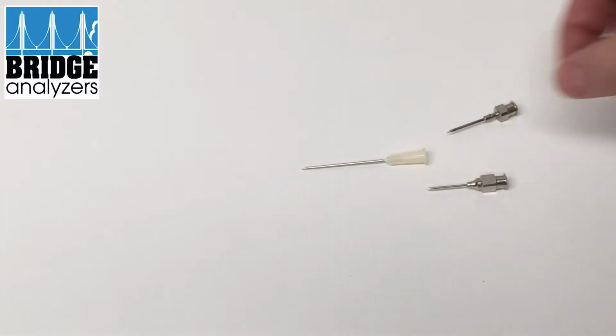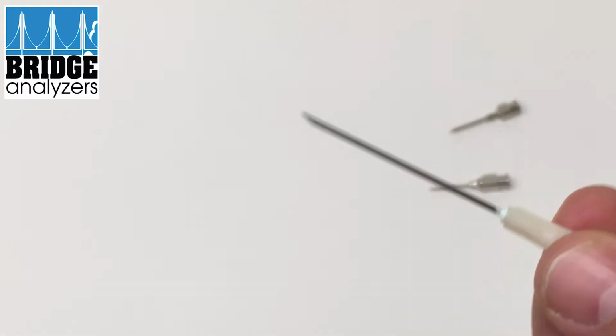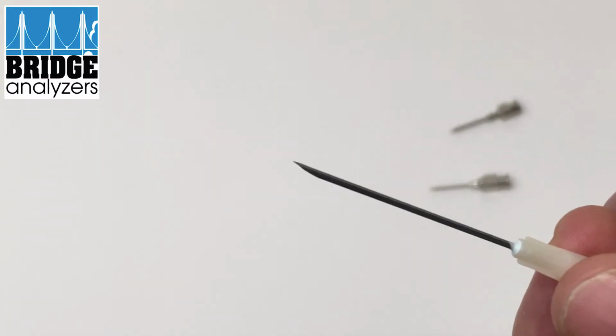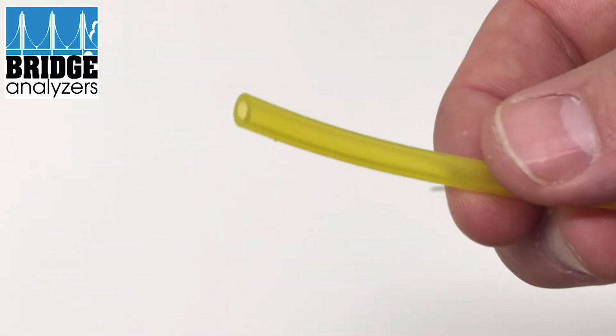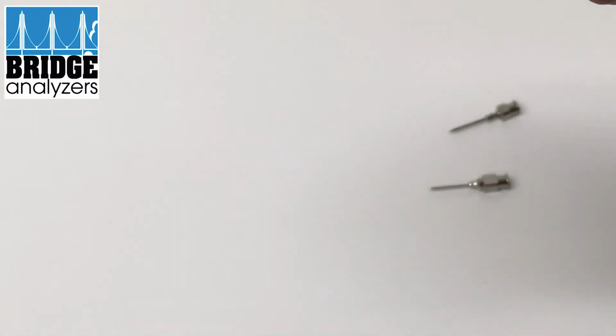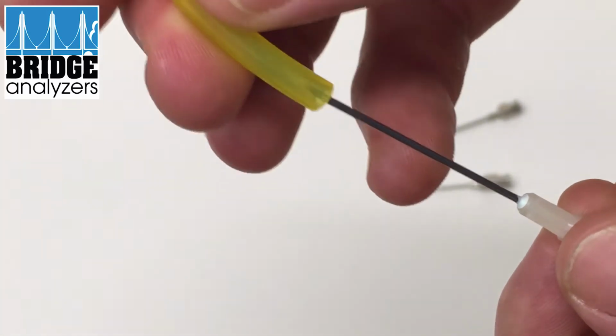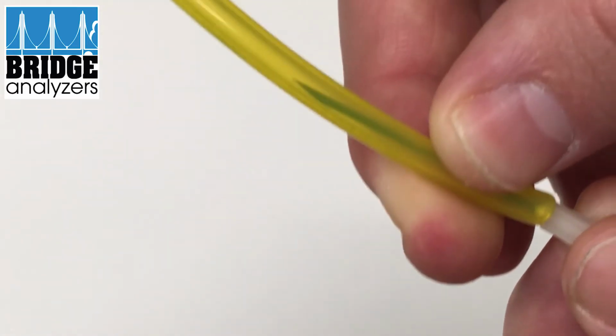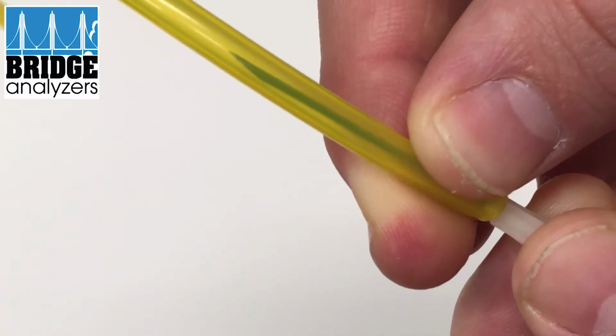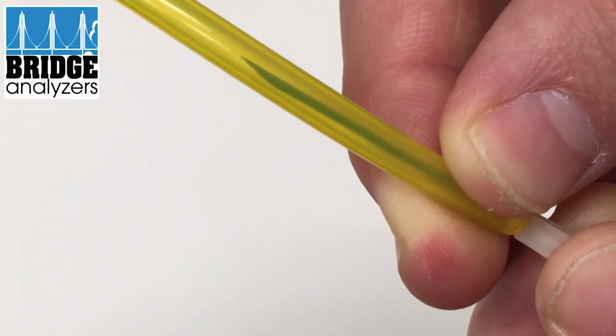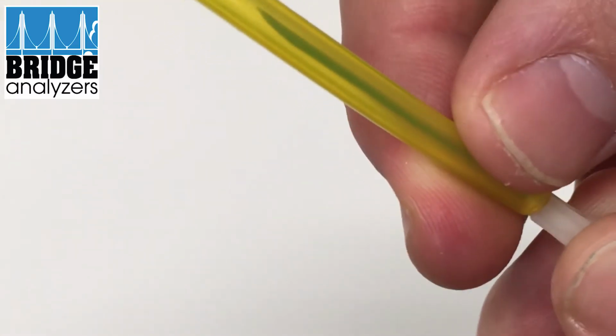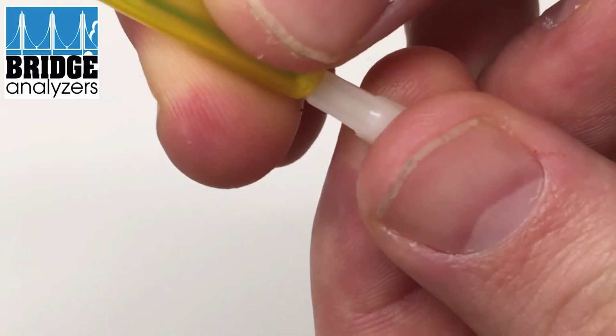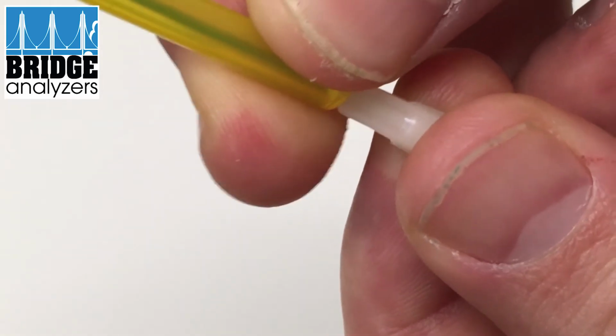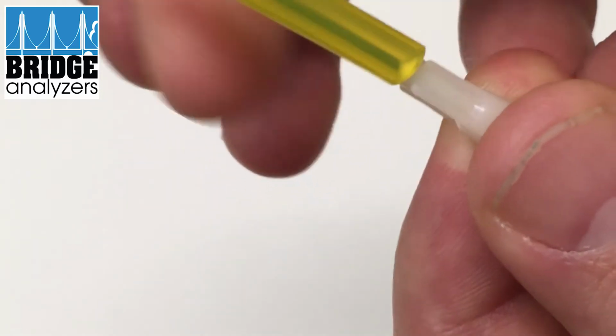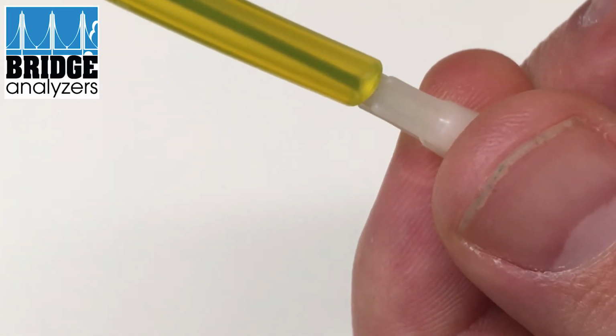If you were to do calibration, which a lot of our customers do, basically you have a calibration test stand with tubing to supply the gas. So what you do is you basically put the needle in the tubing where you're flowing gas, and you need to ensure that you're not drawing in any ambient gas or ambient air to your sample gas. If you're using a hypodermic needle, you really have no way of attaching the tubing to the needle. Even if you try to push it on, it doesn't stay on. So you'll see there's no way to do it.